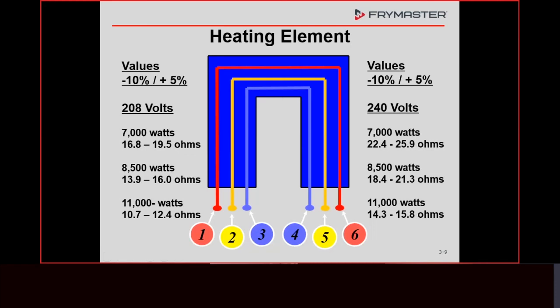On the voltages, you have to make sure that you're installing the right voltage on a fryer. If, for whatever reason, you install an 8.5 kW element in a 14 kW fryer, that's not the end of the world, as long as the service in the store can handle it. The only difference between a 14 kW fryer and a 17 kW fryer is the elements. As long as the service in the store can handle it, that's fine. It's not going to hurt anything.